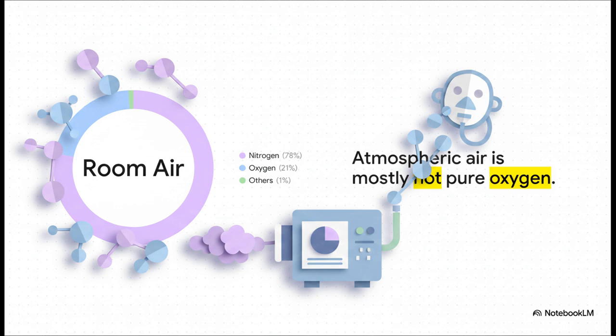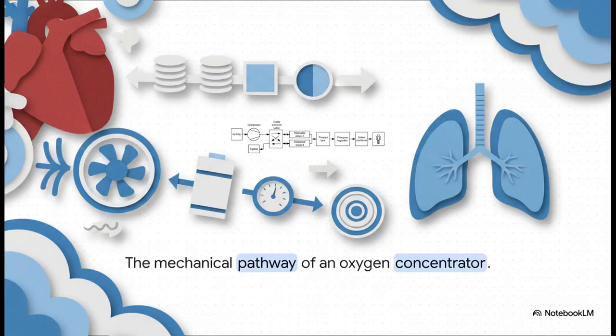At its absolute core, an oxygen concentrator is just an intricate, amazing air separator. And the mechanical pathway inside one of these things is fascinating, because in a way, the machine actually breathes too. The whole process kicks off with a compressor pulling room air inside. You can basically think of this compressor as the machine's combined heart and lungs. It squeezes the air to a super high pressure, forces it through filters to strip away dust and any bacteria, and preps it for the absolute most critical step of the whole journey.